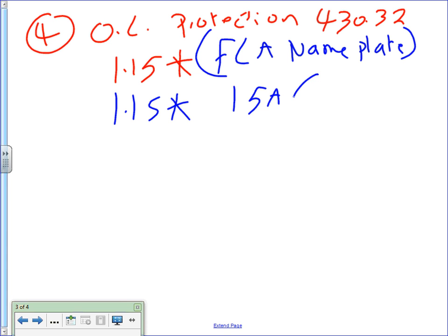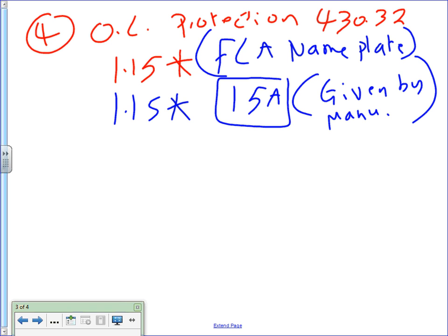Where did they get the 15? Given by manual. Given by manufacturers. I'm giving you that this motor is 15. The full load amps is 15 for it. Can I get you guys to note nameplate full load amps is 15? Given. That's the one that you use. You don't use the one from the table, the 17. Okay, what's the math on that, please?